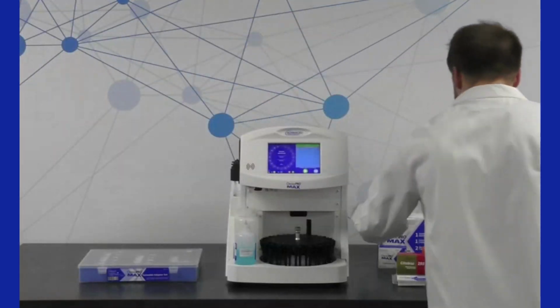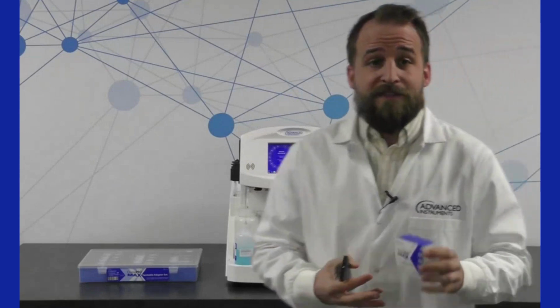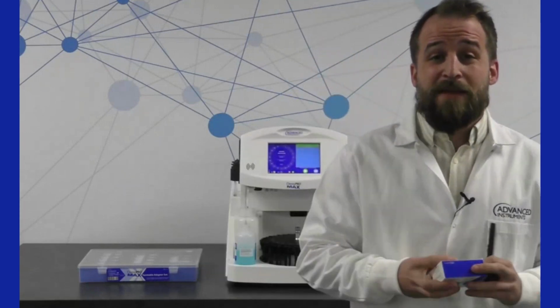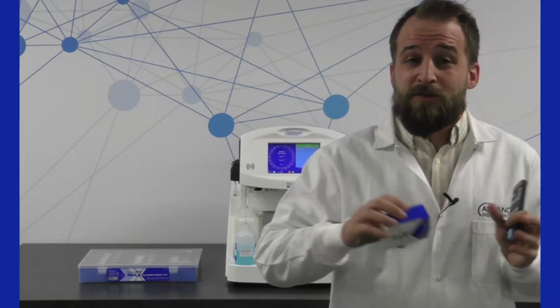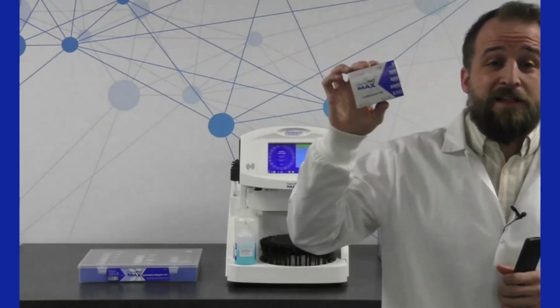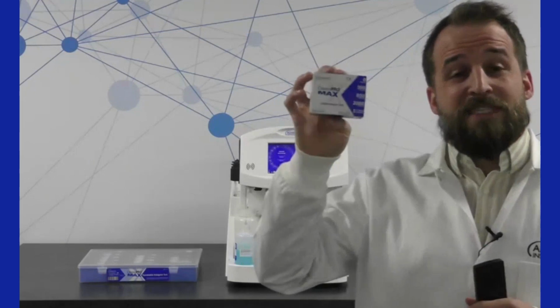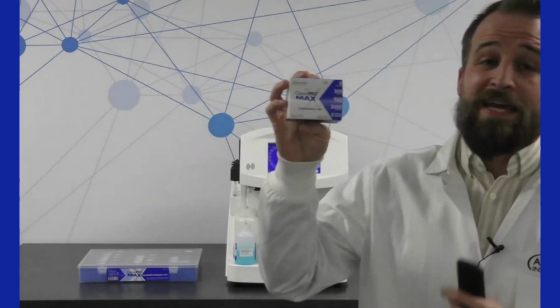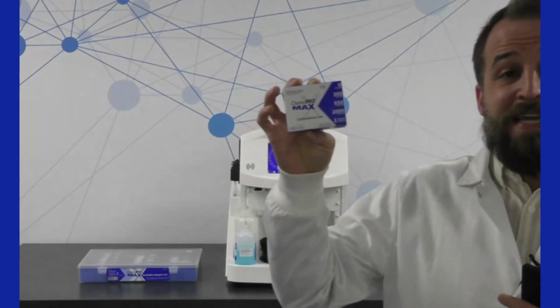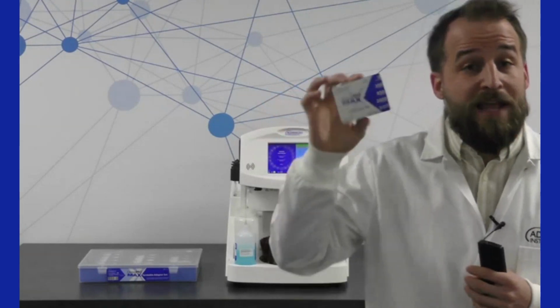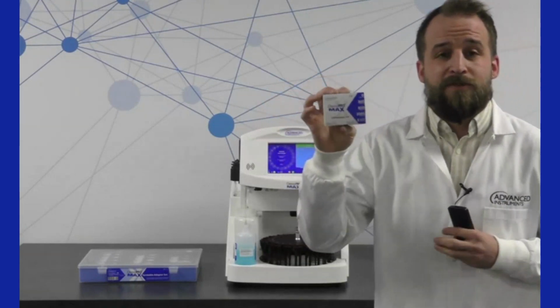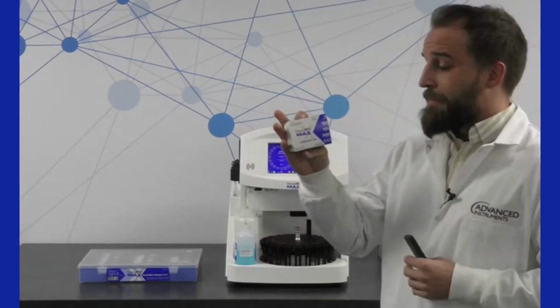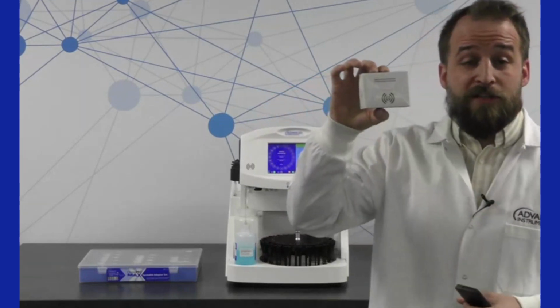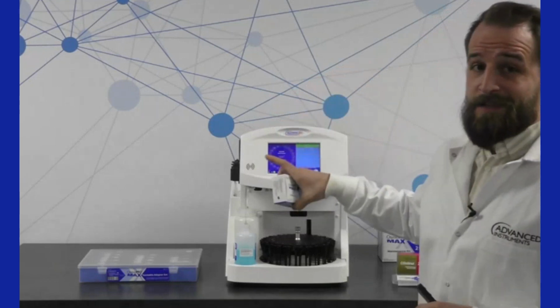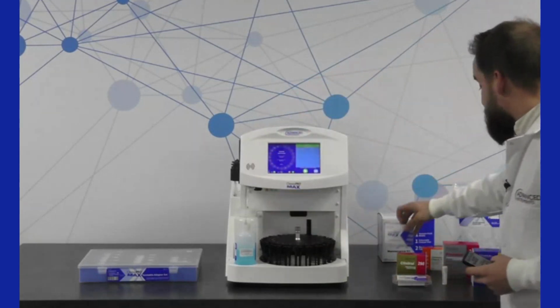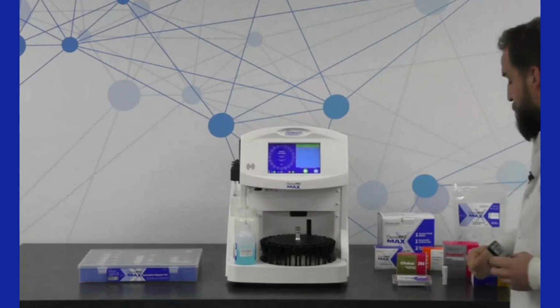So that's the Max 500 kit. Another thing that you'll want to have for this instrument, because we recommend calibration just like most of our other osmometers around every 6 months, is the calibration kit. This is a calibration kit that's specifically packaged for the OsmoPRO Max. It comes with a 0, 300, 850, and 2000 milliosmol standard and an ampule opener, so you can crack open these ampules without worrying about the sharp glass. So it's another one of our consumables that has the RFID tag that you just hold right up to that scanner to initiate that process as well when the time comes for calibration.